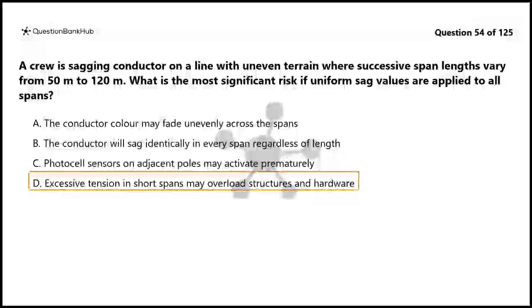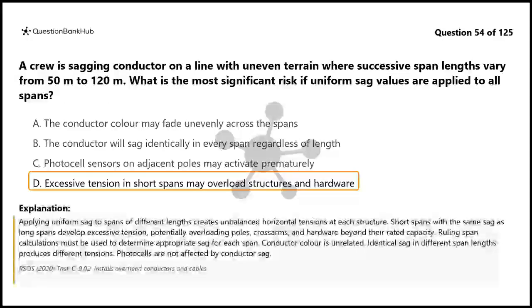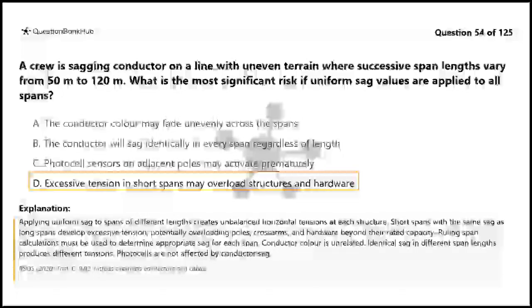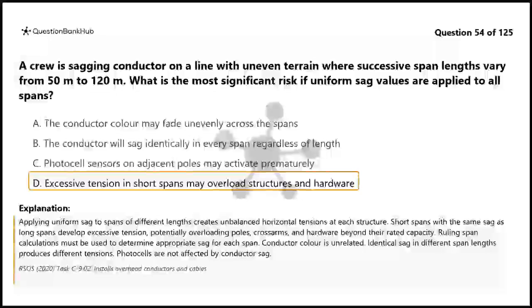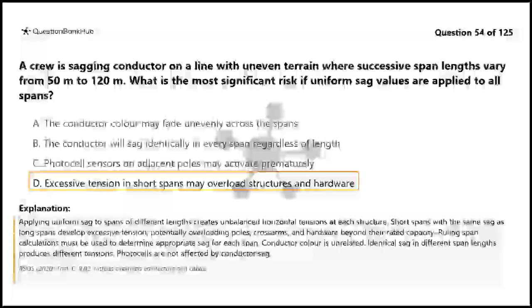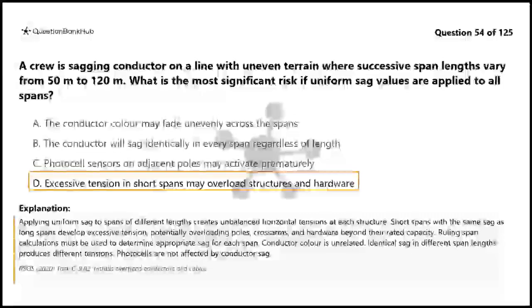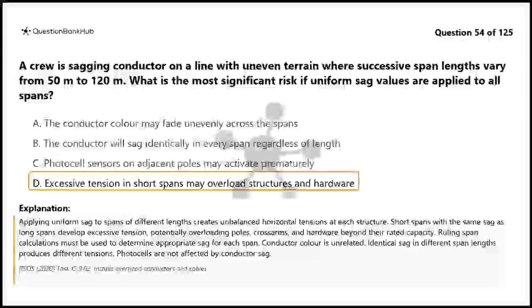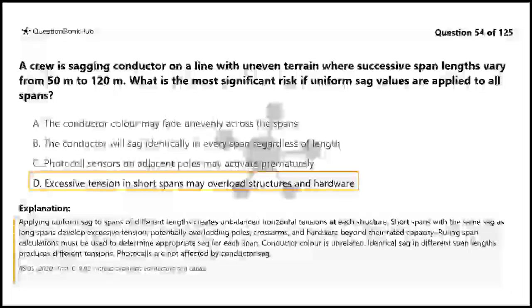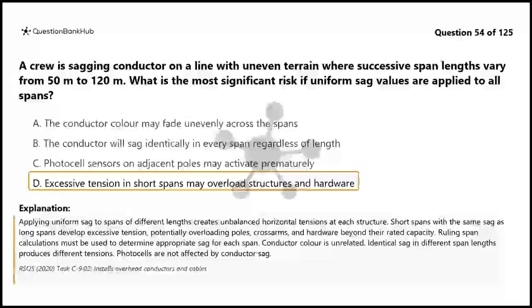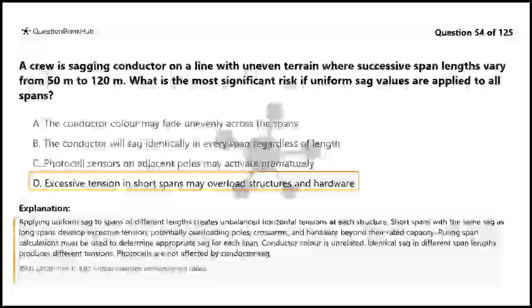The correct answer is D. Applying uniform sag to spans of different lengths creates unbalanced horizontal tensions at each structure. Short spans with the same sag as long spans develop excessive tension, potentially overloading poles, crossarms, and hardware beyond their rated capacity. Ruling span calculations must be used to determine appropriate sag for each span. Conductor color is unrelated. Identical sag in different span lengths produces different tensions. Photocells are not affected by conductor sag.